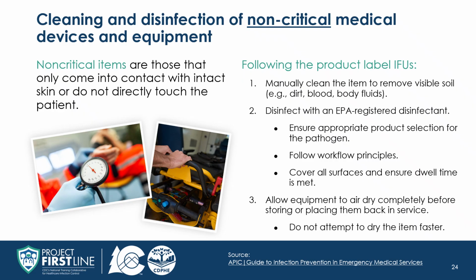To clean and disinfect, first, manually clean the item to remove any visible soil such as dirt, blood, or body fluids. Then, disinfect the device or item with an EPA-registered disinfectant. Disinfectants can come in the form of impregnated wipes or spray. Follow workflow principles and ensure that all surfaces are covered with a disinfectant and remain wet until the dwell time is met. Then, allow equipment to air dry completely before storing or placing it back in service. Remember, do not attempt to dry an item faster.